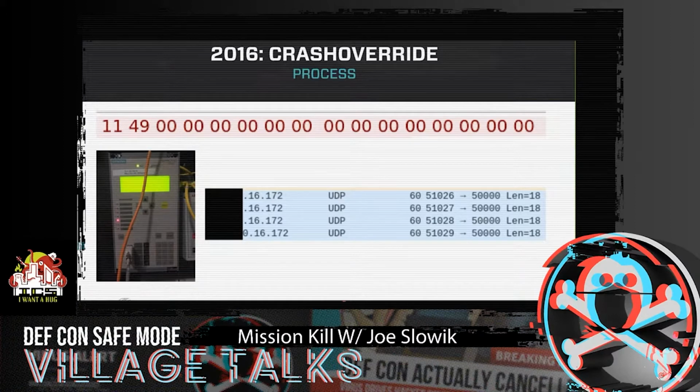It looks powered on. So if you're running through the yard trying to figure out what's going on, or through the control room, it might look like the device is still up and running, but all the actual protection logic is removed, so it's not doing its job. And it's a trivial attack to execute just by sending a single UDP packet within the environment.